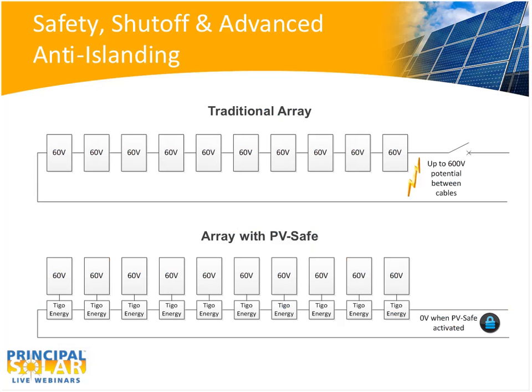The way systems are designed today, there are disconnects at the end of every string. So when you hit the disconnect, there's no current flowing, there's no power being generated. However, there is a voltage potential. So in this simple example, if you've got 10 modules with a 60-volt open circuit, then that open circuit's got up to 600 volts there.